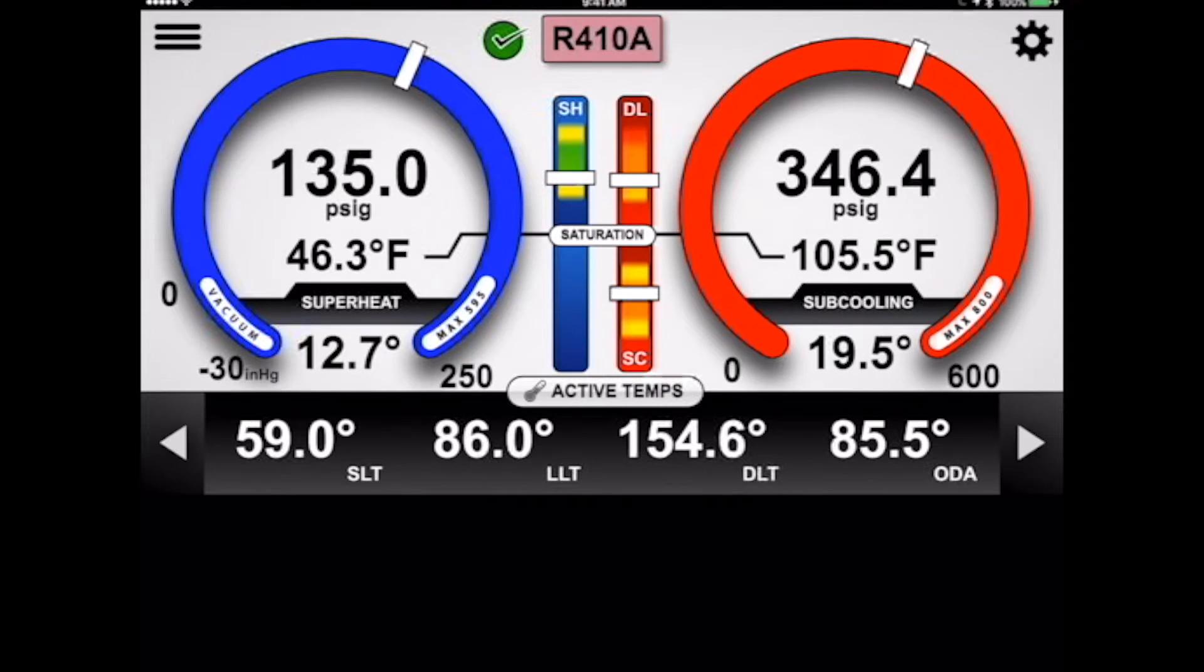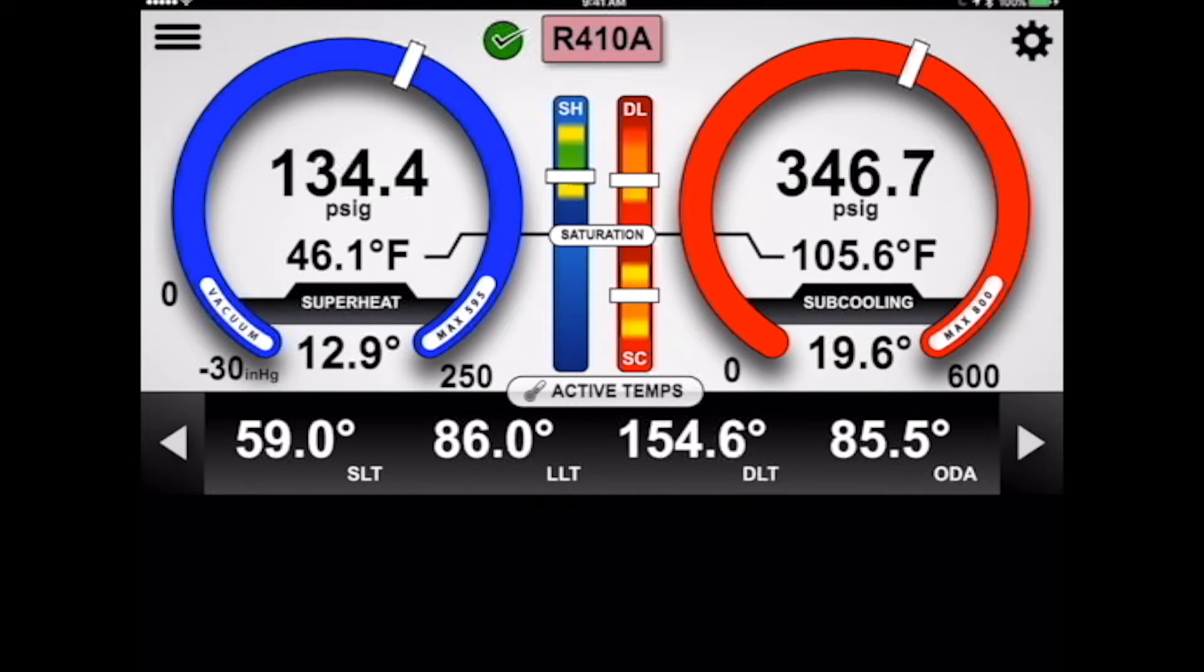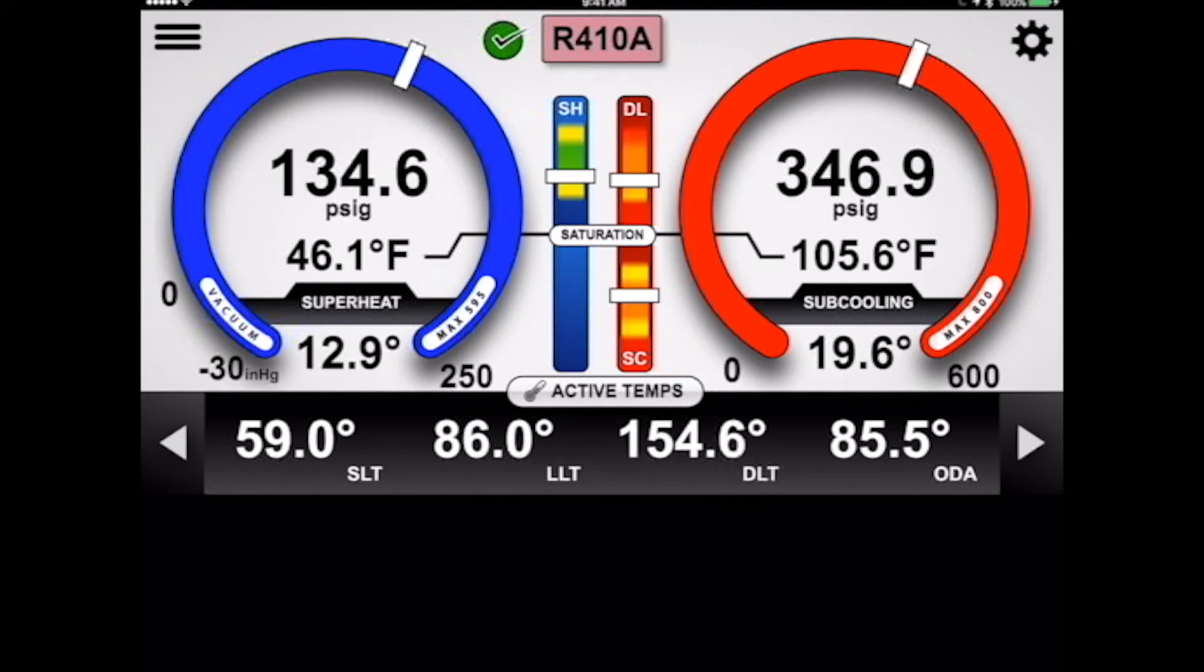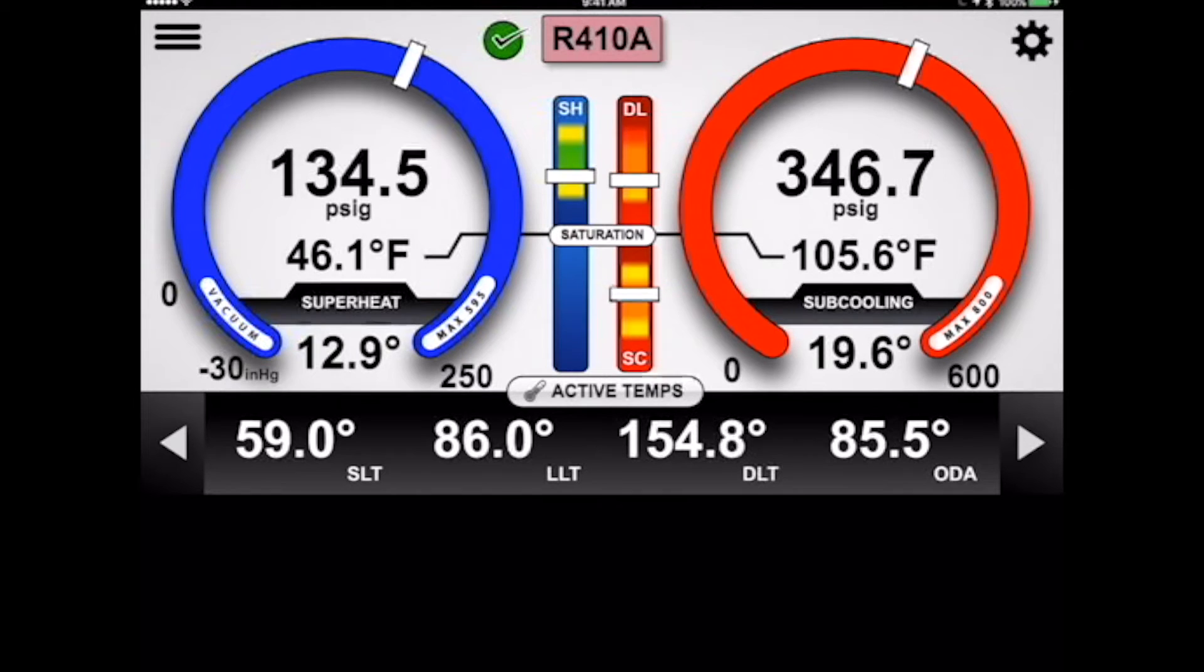So when you think about this, when we're looking at this system operating in our lab right here, you can see we've got our low and high pressure, our saturation temperatures, our superheat and subcooling. But do we really know if this system is even operating correctly? You can see the system is stable, but how is it actually working?